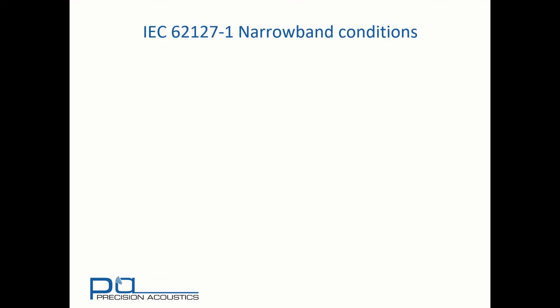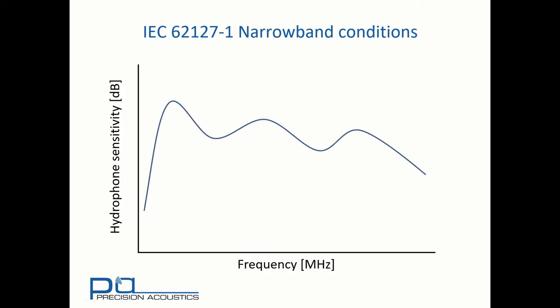It's also important to note that IEC 62127 Part 1 contains another means of converting voltage to pressure, but only when we are subject to narrowband conditions. Consider a hydrophone sensitivity function as shown.